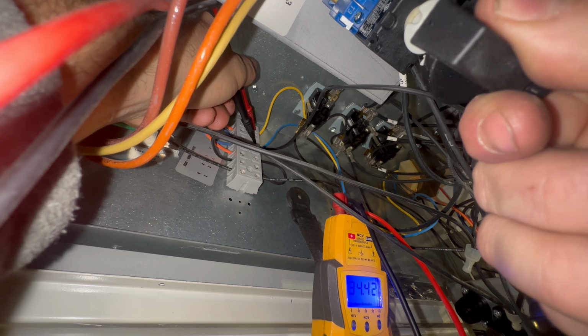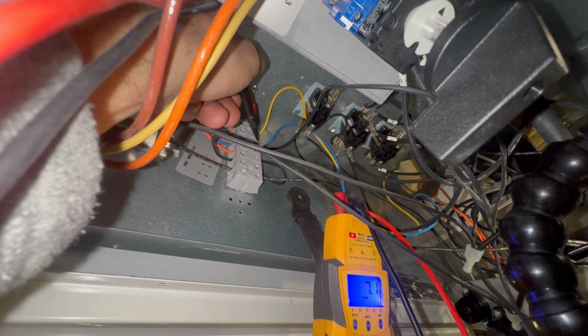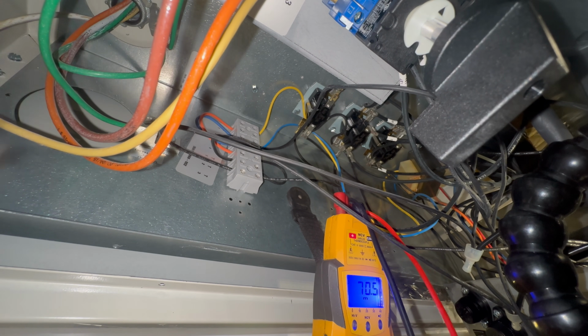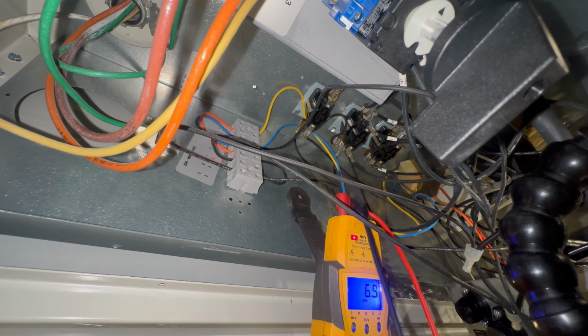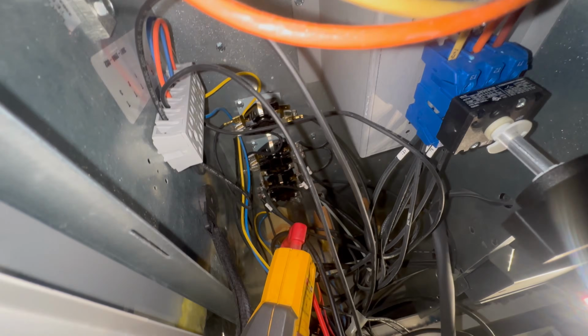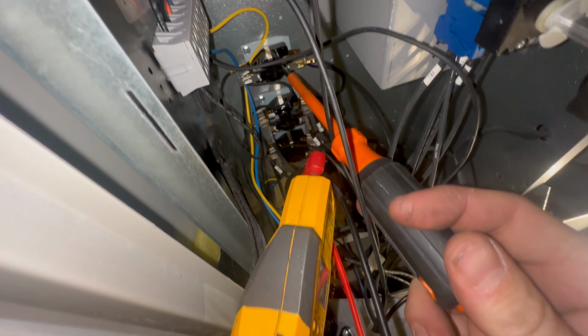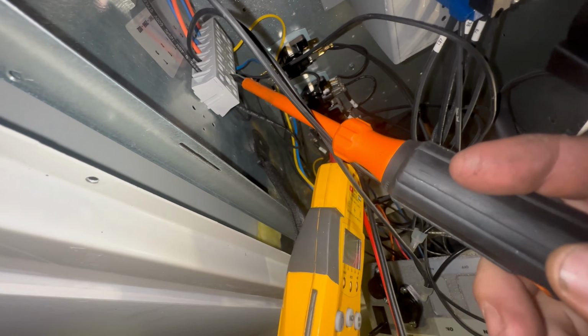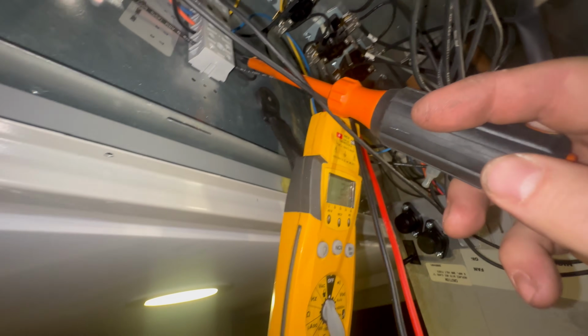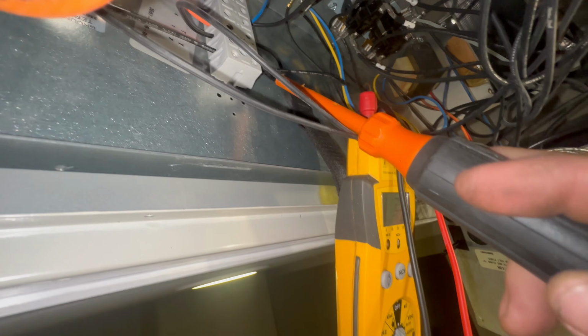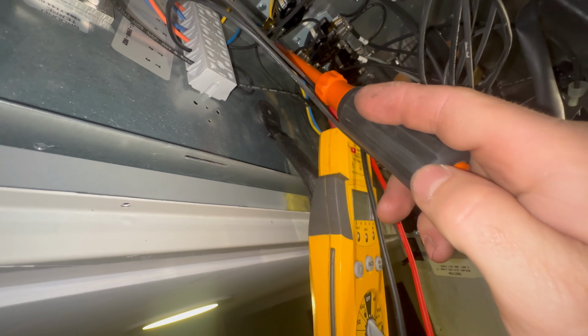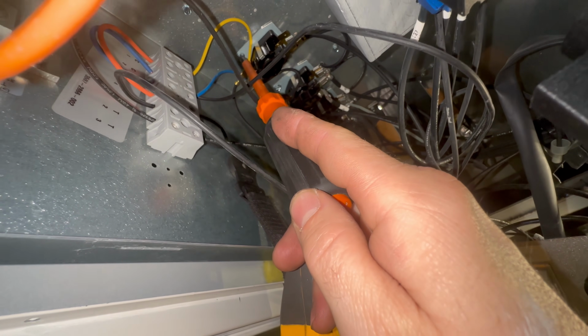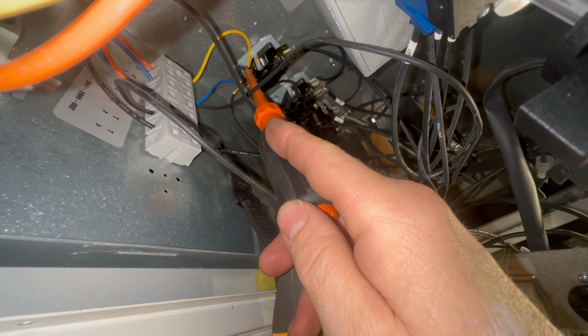34 volts. That is awfully high, but that's not our issue. Here are our 3 relays. If I trace these wires out, we can see that we have one from right here that goes straight back to the heating relay, 24 volt coil.